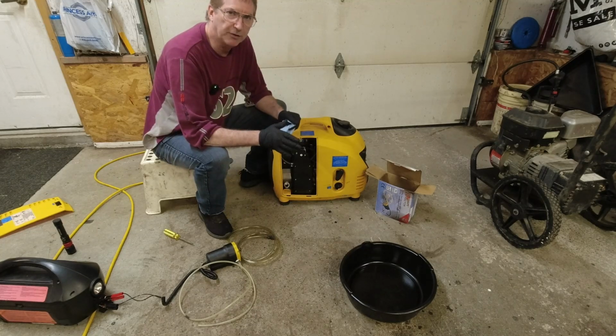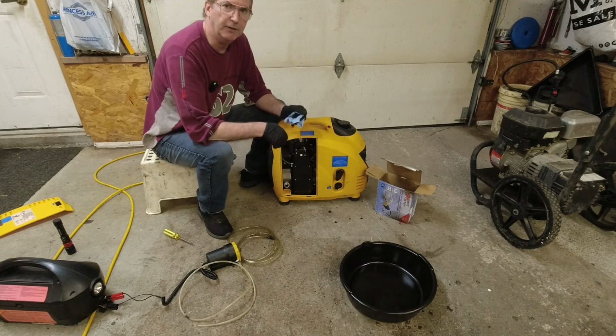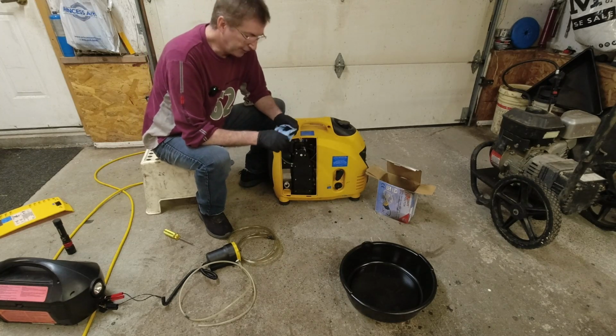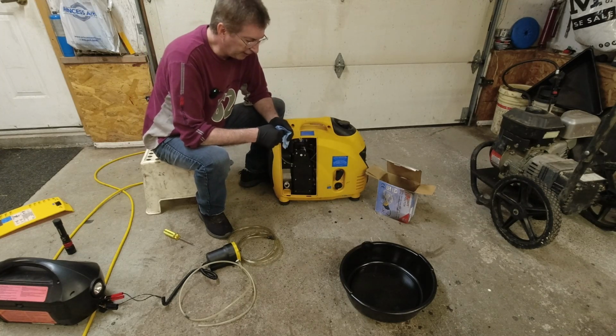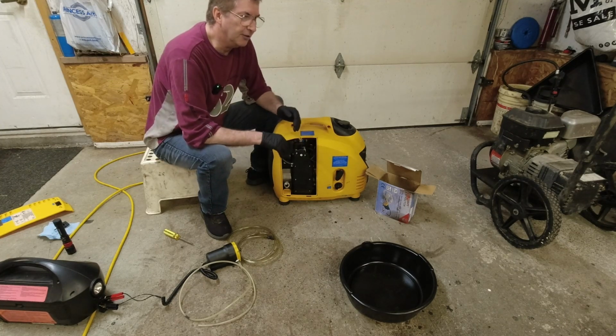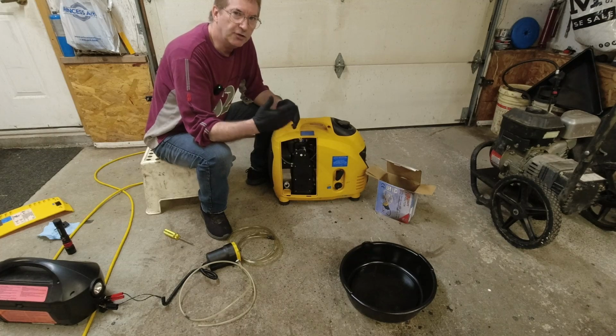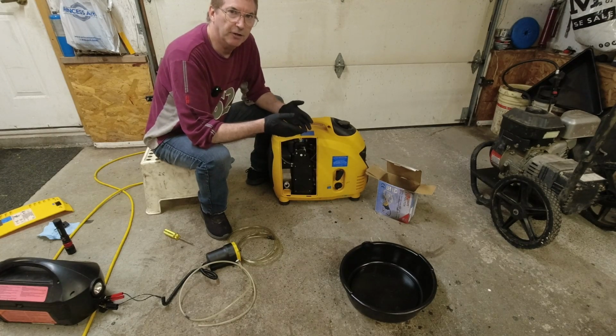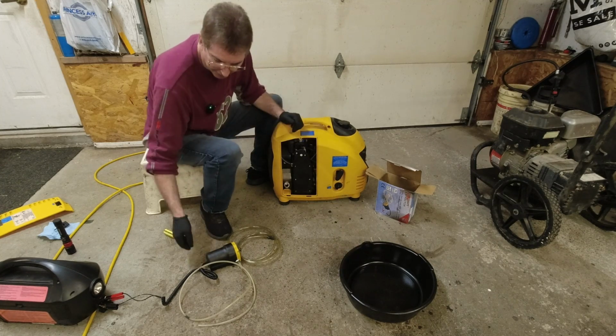If you end up with a power failure, obviously you don't wait for 2 years to change oil. You change it after so many hours. Check the manufacturer, see what they request. A lot of times it's 100 hours or 50 hours. If you don't use it in 2 years, you still, every 3 months, you should still start the engine. If not, let's say 5 years down the road, you try to start it, it just may not start.